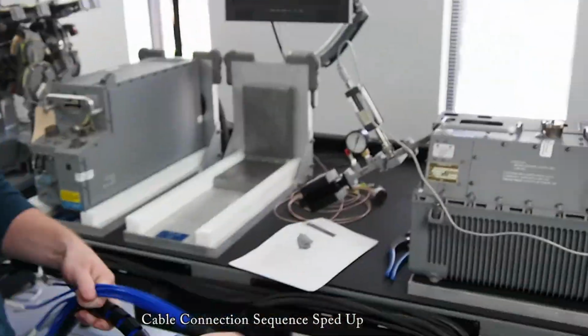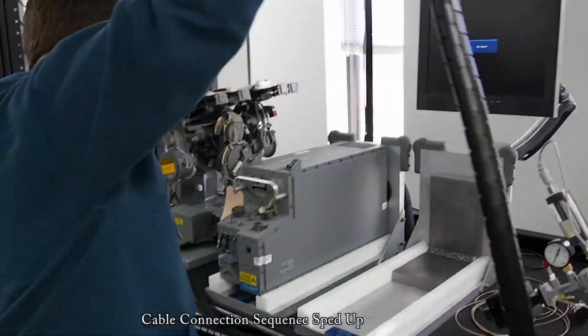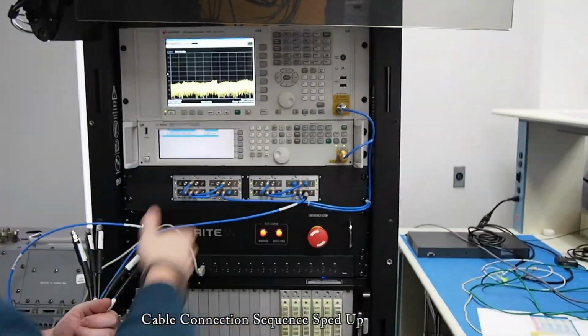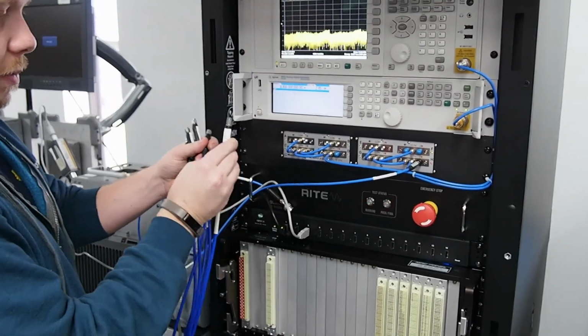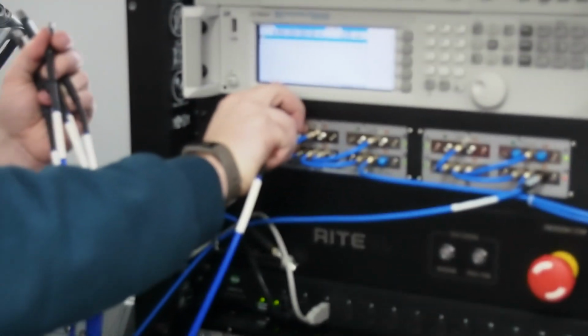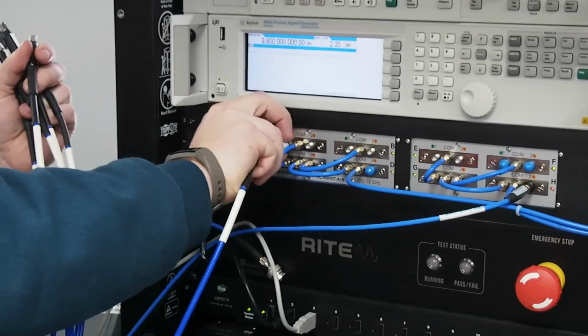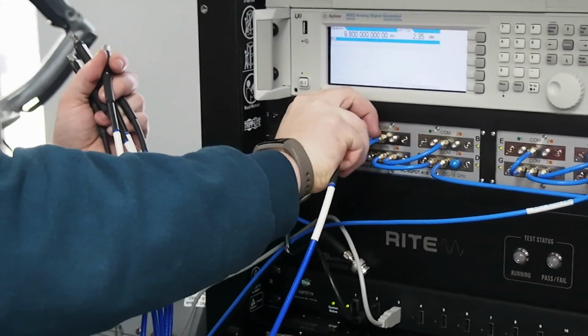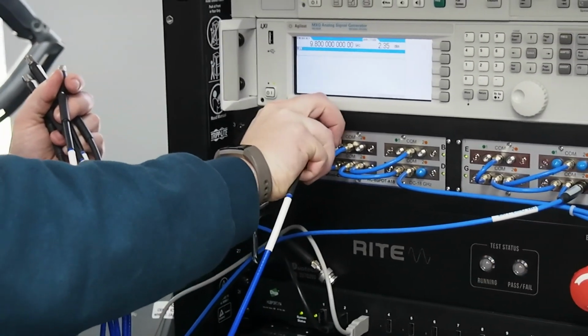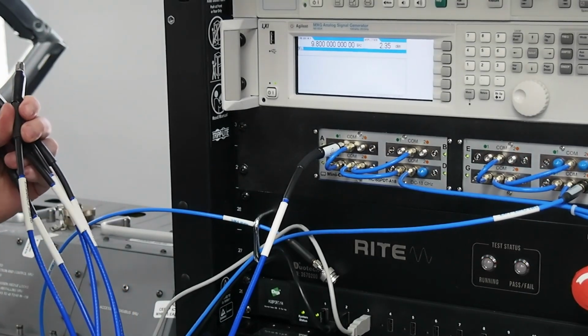Here we see the RF connections being hooked into the switch. This routing switch is utilized such that the RF measurement and source signals can be routed by the test program. In this routing switch, we have all of the required connections for the infrastructure connected, and we are hooking up the test specific RF connections.